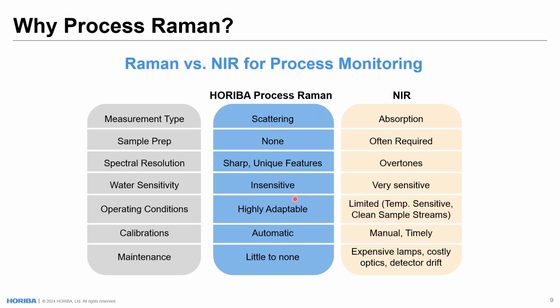It's very sensitive to temperature. There can't be a lot of particulates or other things that may interrupt a sample stream, which would throw off the collection of that data for NIR spectroscopy, whereas process Raman is way more adaptable to those sort of unexpected changes. Calibrations for HORIBA Process Raman, I'll get into this a little bit later, are all automatic. There's nothing that the end user needs to do before they collect the spectrum. The software runs through it automatically, whereas in a lot of NIR spectroscopy, the calibrations are manual and time-consuming, and this goes into the maintenance that is expected with NIR analyzers.